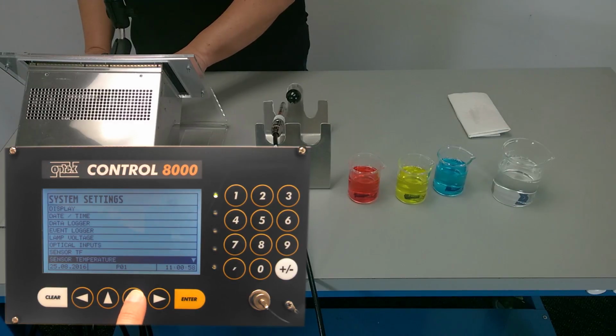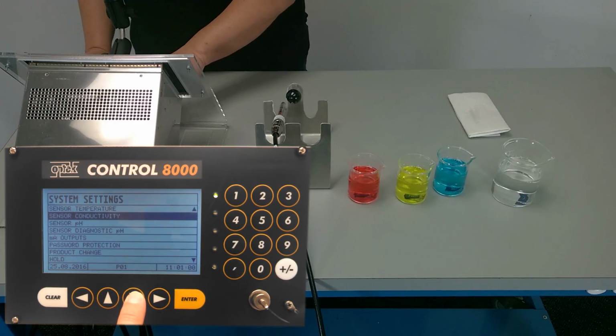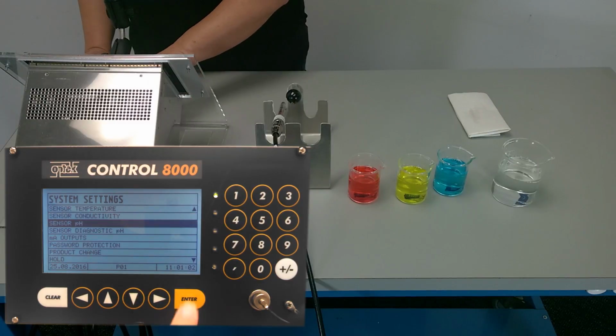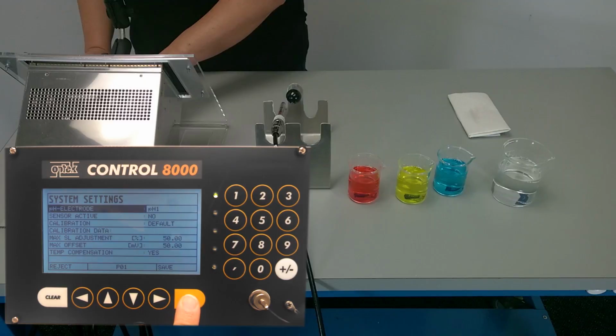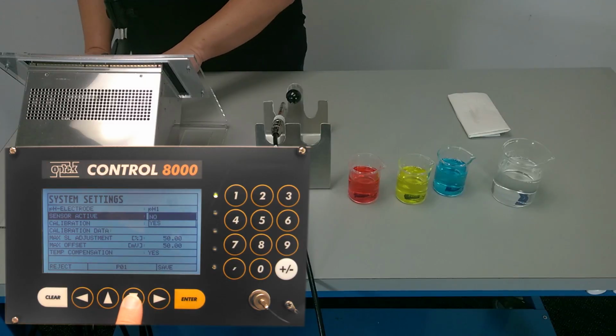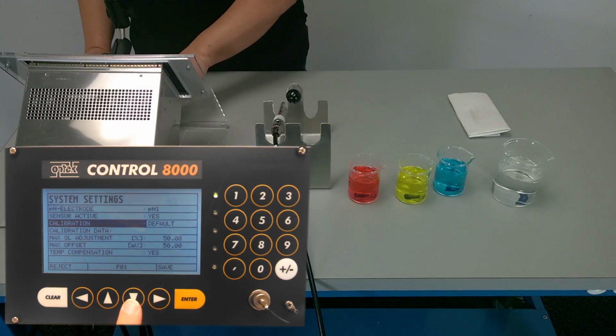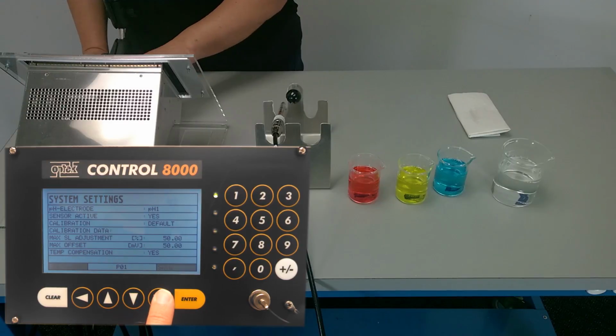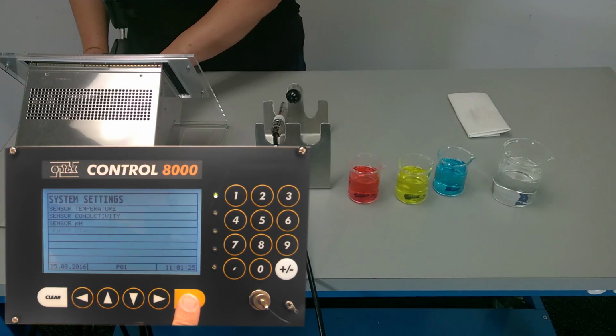And then we are going to hit the down arrow a couple more times and get to an additional set of menus. We are going to hit Enter for Sensor pH. And as I said, we are going to use electrode pH1. So hit the down arrow for sensor active, hit Enter to yes. Calibration, we are going to leave set to default. Once we do a pH calibration, we will go back and change this to user. So for now, scroll to save and hit Enter.